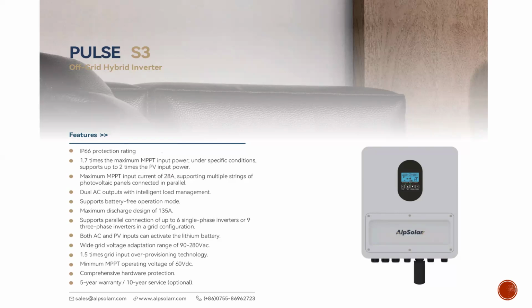Also, it has a wide grid voltage adaptation range of 90 to 280 VAC. This is very perfect for the Nigerian electricity. For most parts of Nigeria, we have an unstable grid, and that means we have unstable voltage. So this inverter is built to work with low voltage and even high voltage. As low as 90 volts, the inverter is working fine, taking input from the grid, and as high as about 280 volts, this guy is still working fine.